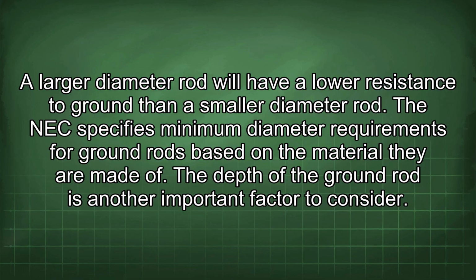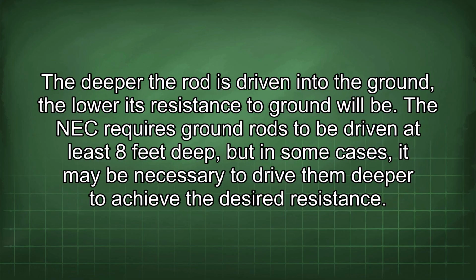The depth of the ground rod is another important factor to consider. The deeper the rod is driven into the ground, the lower its resistance to ground will be. The NEC requires ground rods to be driven at least 8 feet deep, but in some cases, it may be necessary to drive them deeper to achieve the desired resistance.